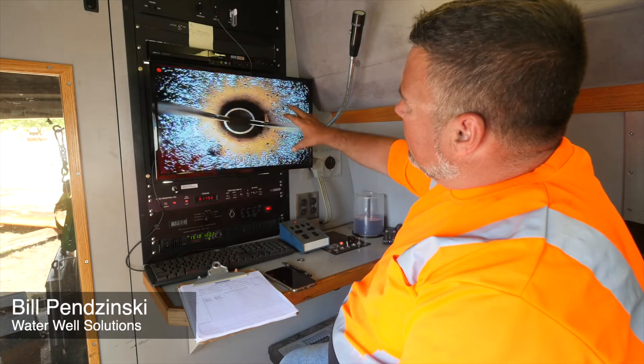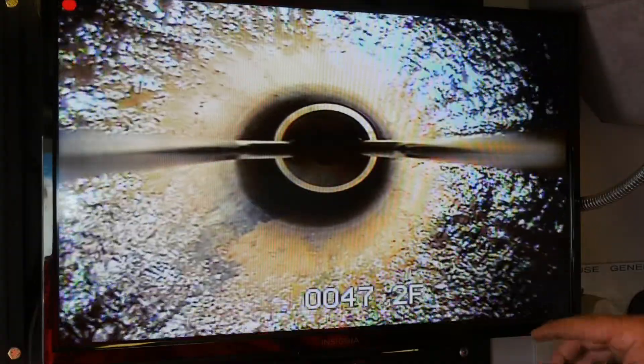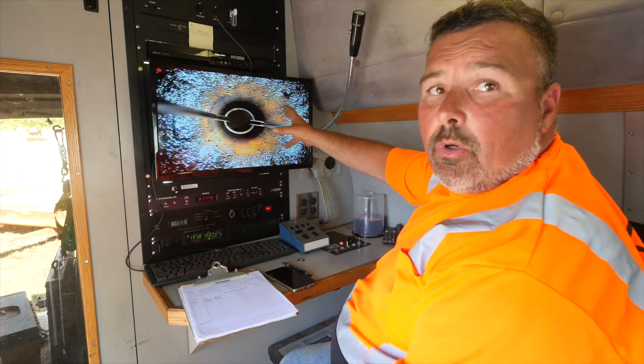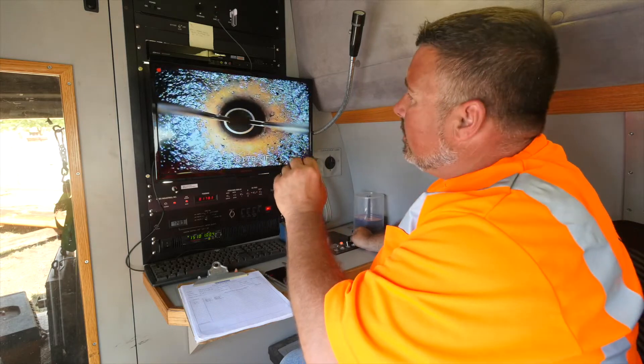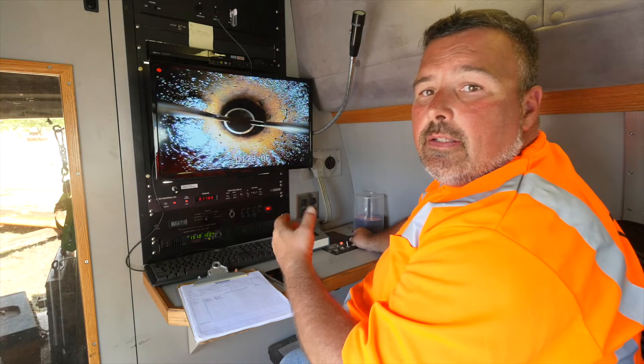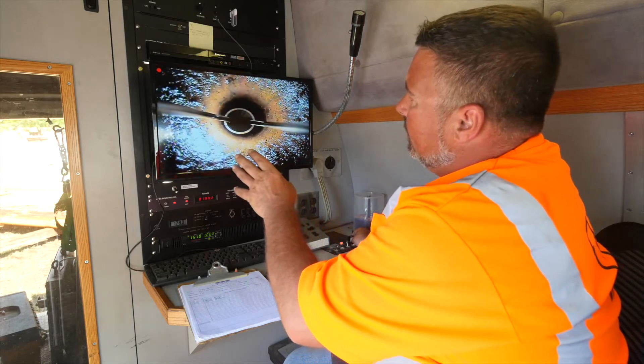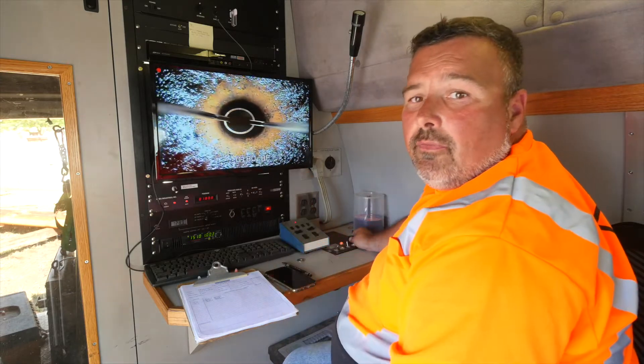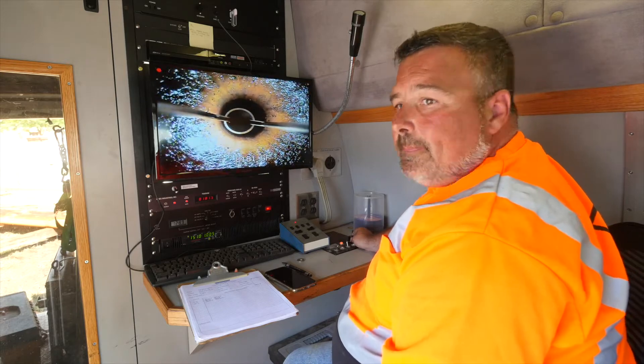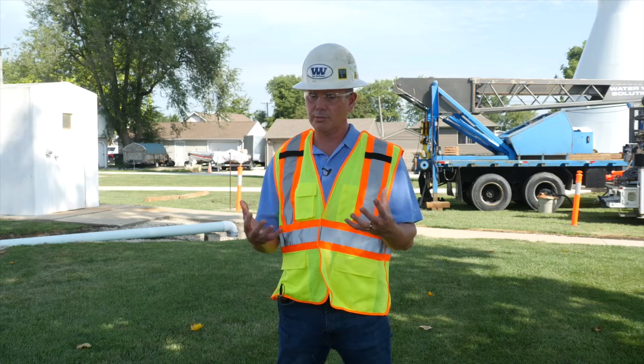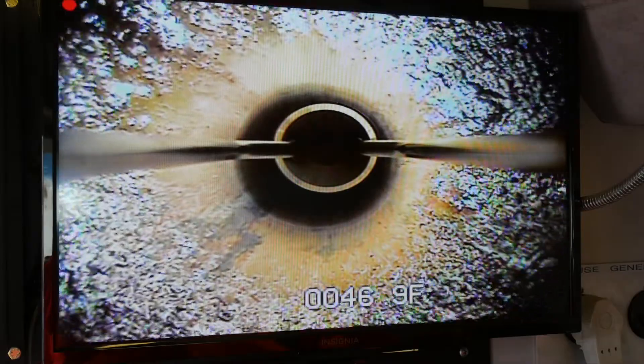We're looking at the well casing, looking for different bacteria and different colors of bacteria. We're looking at the condition of the casing, making sure there are no holes or any kind of flaking. If there's a lot of flaking, we can come in with a Cody brush or a steel brush and knock the rust and flaking off. If it's really bad, we'll do a second survey to make sure there are no holes in the casing. This casing's flaking is not really bad — we're seeing a lot of barnacles which look like they have bacteria involved. That's where the chemical treatment and brushing will come into play. Sometimes it's easier to do the mechanical work first and remove all that bacteria and silt sedimentation, then follow through with a chemical application, because if you treat it mechanically first you don't need as much chemistry to be effective in the borehole. It's all about working within the client's budget while being very effective in what you're doing.